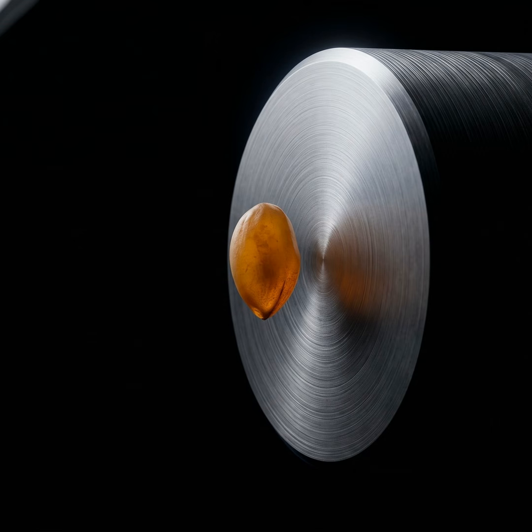If a physical bearing is starting to seize up due to a lack of lubrication or microscopic wear, it creates more mechanical resistance on the drive shaft. Right, it's harder to turn. Exactly, so the electric motor has to work harder to overcome that new resistance just to maintain its required 2,700 RPM. Oh, I see, to work harder the motor must draw more electrical current or amperage from the grid.